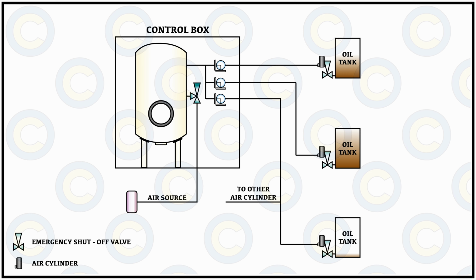So now, as I originally told, a QCV would only be triggered when an air pressure or a force of air comes in and triggers it. That means in its original state, the quick closing valve is always without air pressure. Now, why so? It is important to understand this especially because we want our quick closing valve to be a fail-safe mechanism. So, if it would have been a situation where we are always keeping the actuator triggered by the supply or the pressure of the air and thus keeping it in an open state.